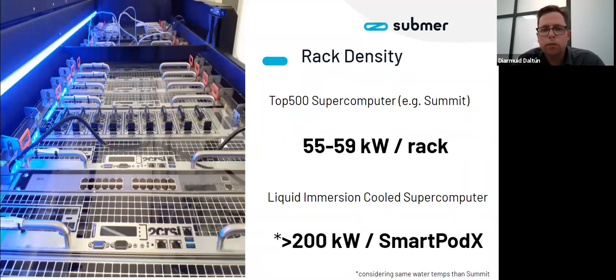There is liquid cooling, a water loop taking away the heat from the system. That water loop is chilled part of the year, and economized water for most of the year, achieved with dry coolers. But if we take the same water loop temperature at which Summit is run and apply that to our technology, specifically plugging that same water loop into the smart pods, we can achieve more than 200 kilowatts per smart pod.